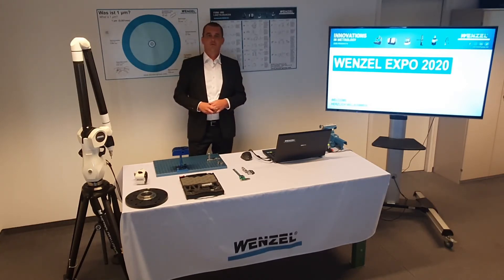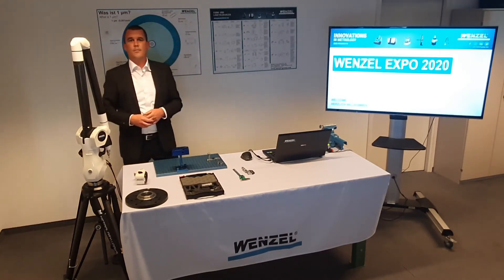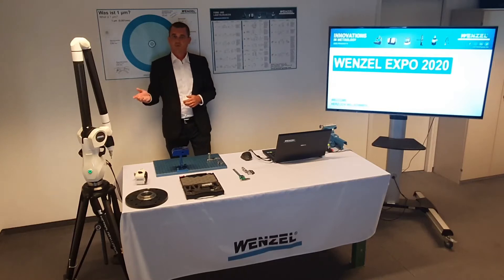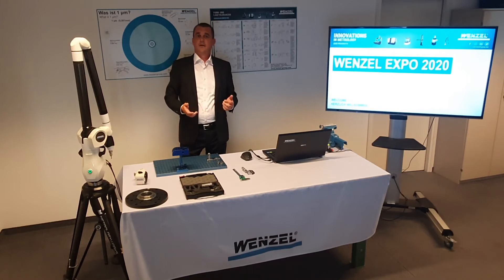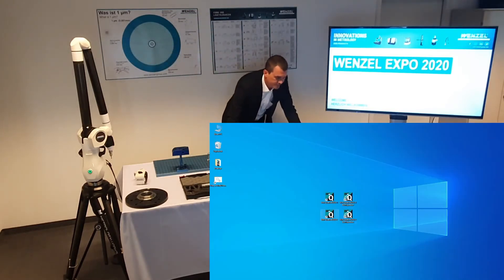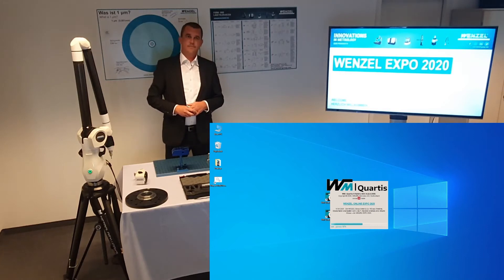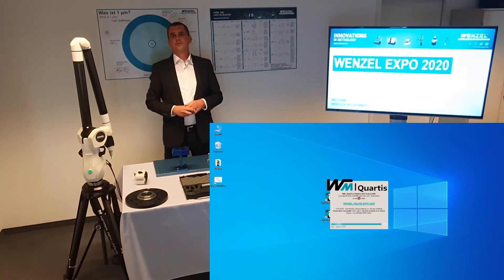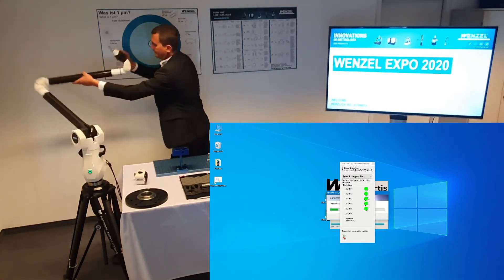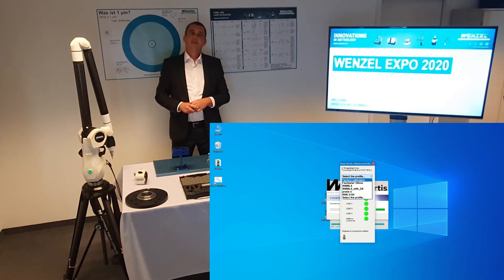I will now show you the arm in practical application with WM Quartis Mobile. I start the arm using the power button on the front side. The arm is connected to my laptop with a USB cable. After switching on the measuring arm, I start the measuring software WM Quartis Mobile. When starting, I am asked to initialize all seven axes. The green traffic light on the computer shows the successful initialization of the axes. When all seven axes are initialized, the arm is ready for use.